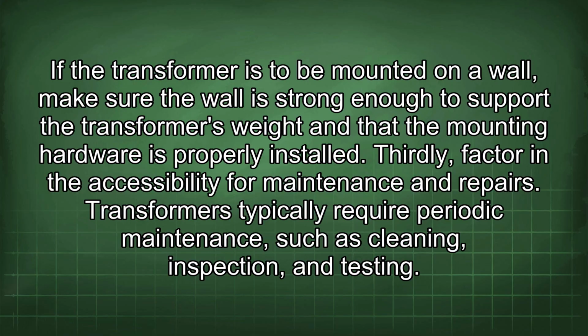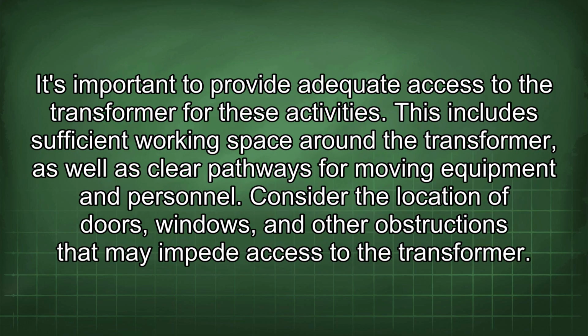Thirdly, factor in the accessibility for maintenance and repairs. Transformers typically require periodic maintenance, such as cleaning, inspection, and testing. It's important to provide adequate access to the transformer for these activities. This includes sufficient working space around the transformer, as well as clear pathways for moving equipment and personnel. Consider the location of doors, windows, and other obstructions that may impede access to the transformer.